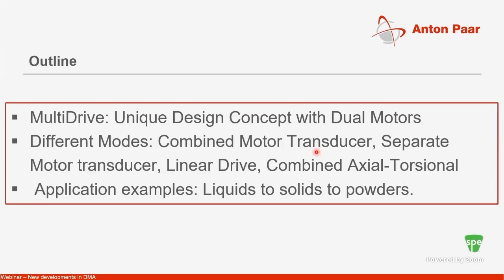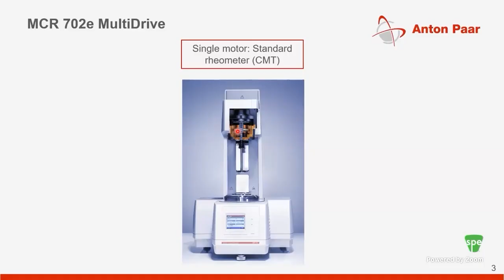Now let's talk about the multi-drive device a bit more. This center picture is a traditional MCR, or modular compact rheometer — a single drive rheometer system, where you see the electronically commutated EC motor in the upper chassis. This is the traditional controlled stress rheometer we're all familiar with. Looking at the mechanics, electric current is applied to the motor, building up a magnetic field which drives the drive shaft.